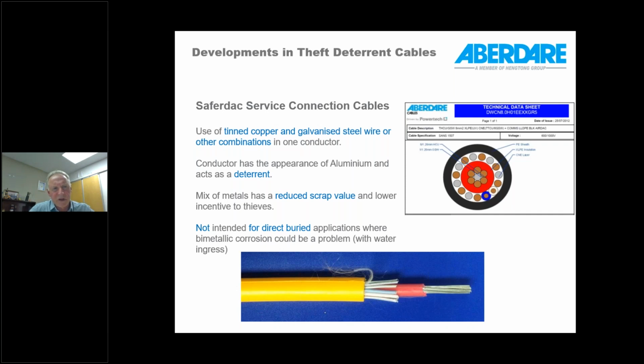We mentioned earlier the Saferdac service connection cable that was developed together with Eskom. We make use of mixed metals, to use that general term. So inside of the cable construction are wires of tin copper and galvanized steel, and this serves as a deterrent, because the mix of metals are not that easy to distinguish. Some customers even refer to it as aluminium cable.